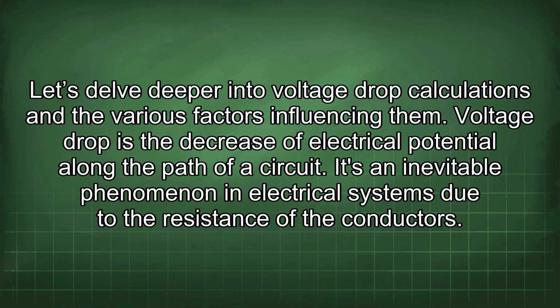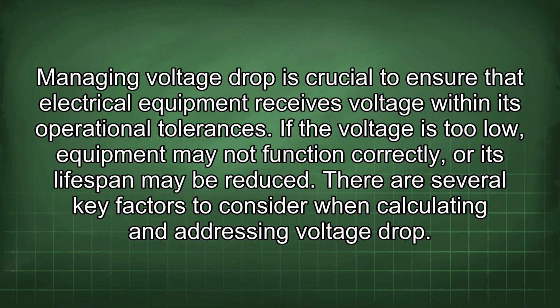Voltage drop is the decrease of electrical potential along the path of a circuit. It's an inevitable phenomenon in electrical systems due to the resistance of the conductors. Managing voltage drop is crucial to ensure that electrical equipment receives voltage within its operational tolerances. If the voltage is too low, equipment may not function correctly, or its lifespan may be reduced. There are several key factors to consider when calculating and addressing voltage drop.